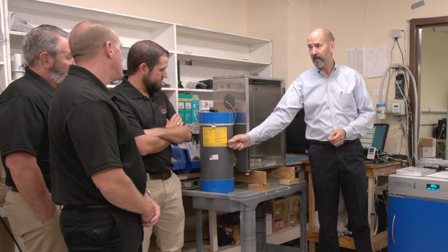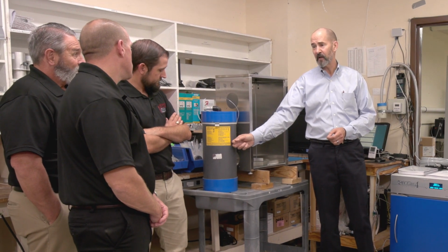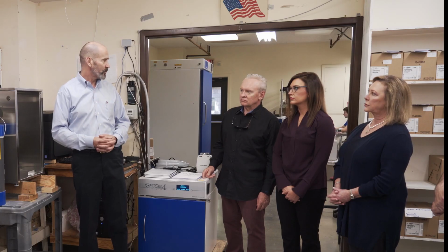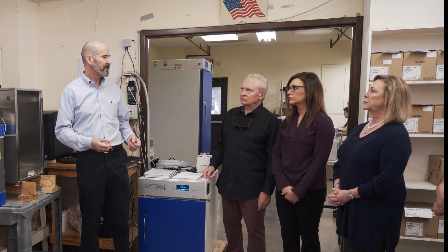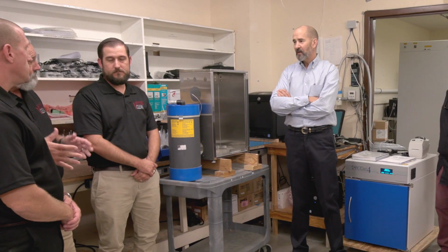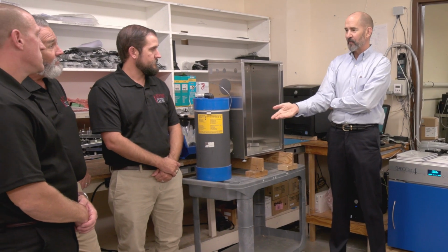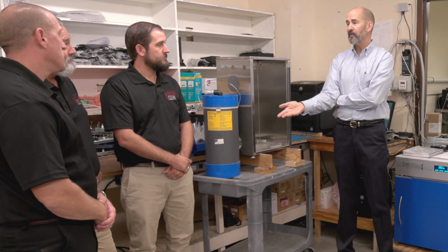And we are unique in the sense that we have a dry chemical bed that captures the ethylene oxide. Most emissions control equipment burns the ethylene oxide. And ethylene oxide is potentially explosive, so burning it can be problematic. Ours is a much simpler system. If you go into an acute care facility, a big hospital, the abater is 5 times this size. So the footprint that you're using to save space for everything is... The abater is 5 times the size and it's 10 times the cost.